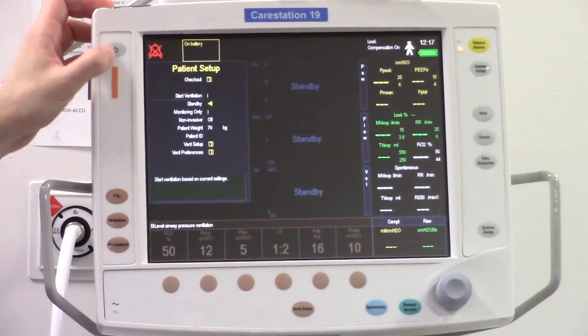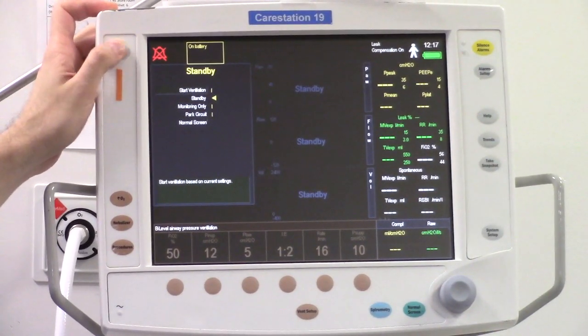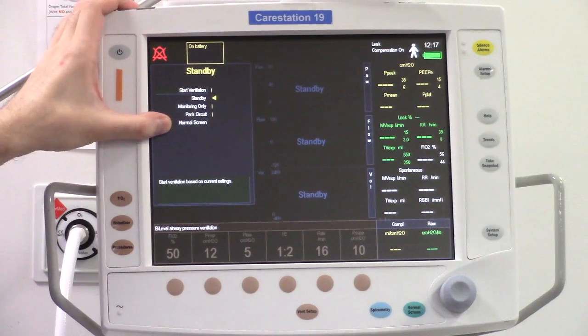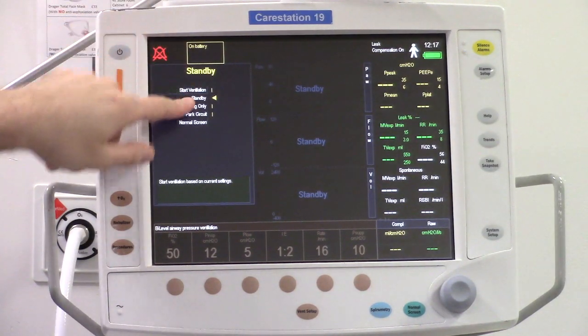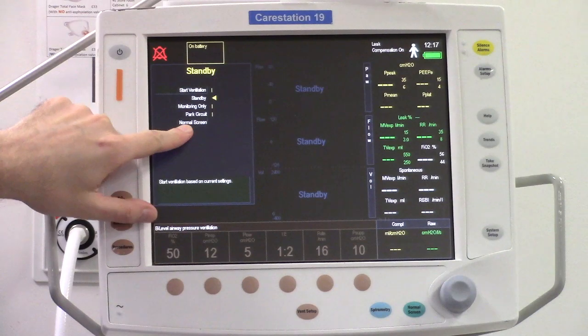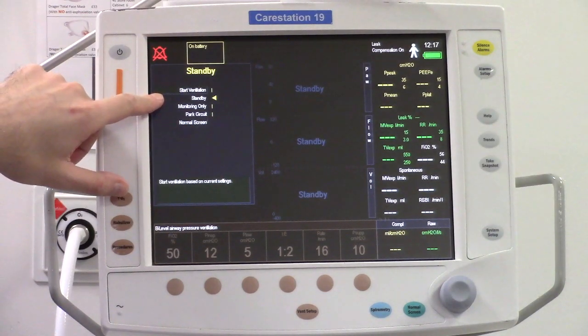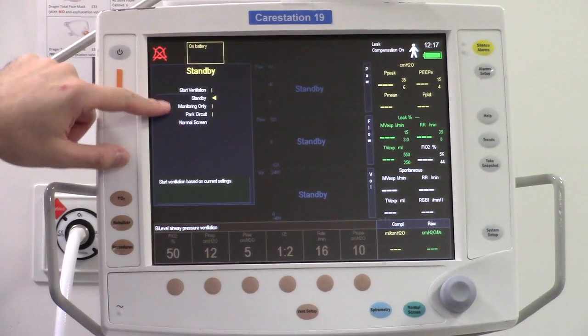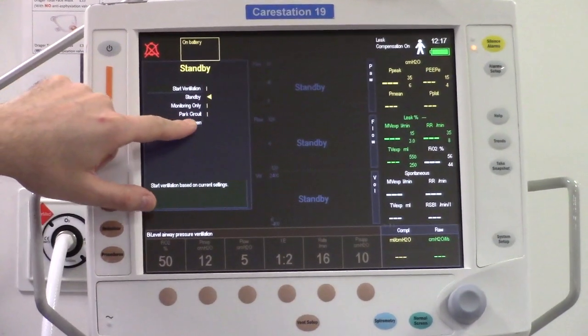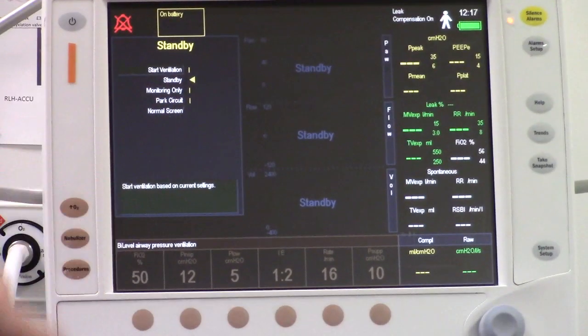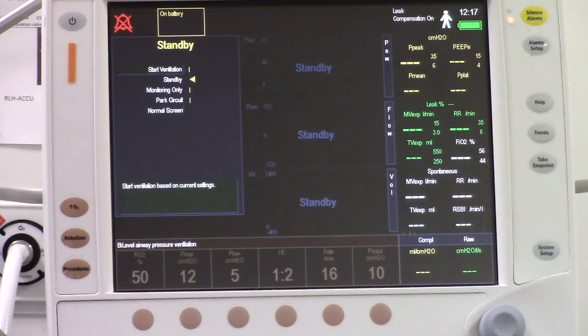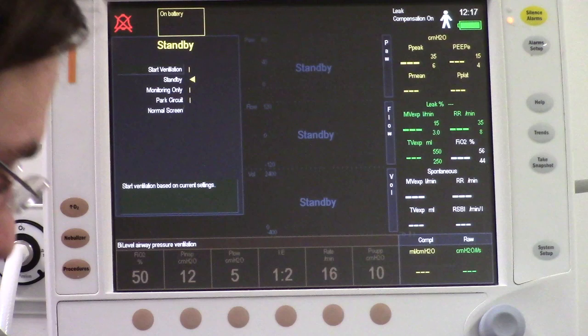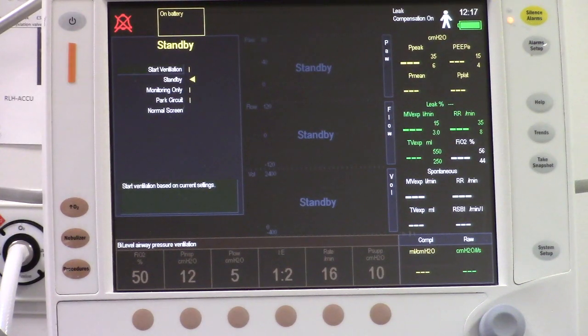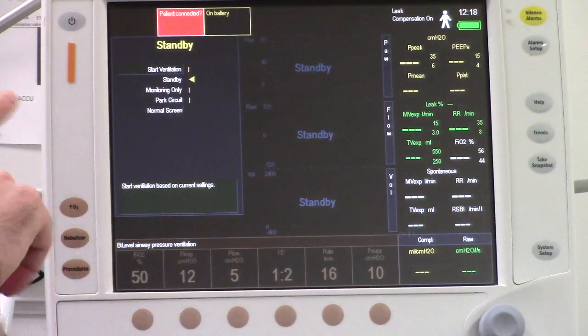This button is called the standby button. When you press it, you'll get this menu, and if it's ventilating, you can stop the ventilation. If it's not ventilating, you have the option of starting the ventilation, obviously, or you can put it on park. You park the circuit, yeah? Because sometimes nurses will stop the ventilation on the patient, they'll connect it there, but it will alarm, yeah, thinking that it's connected to the patient. When you put it, you hear the alarm, yeah?